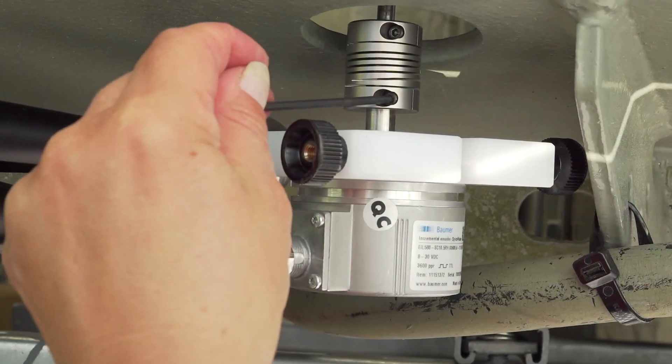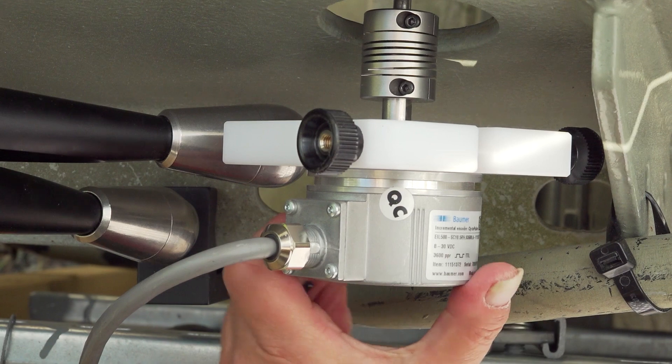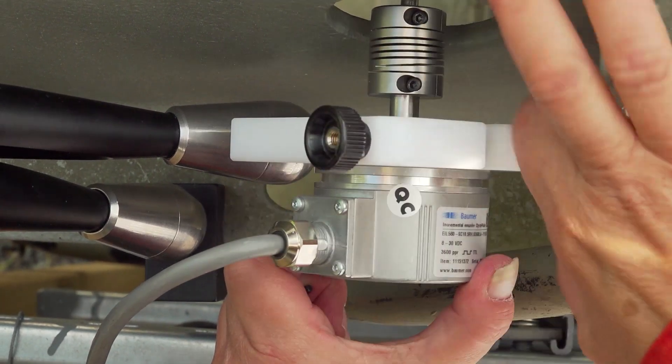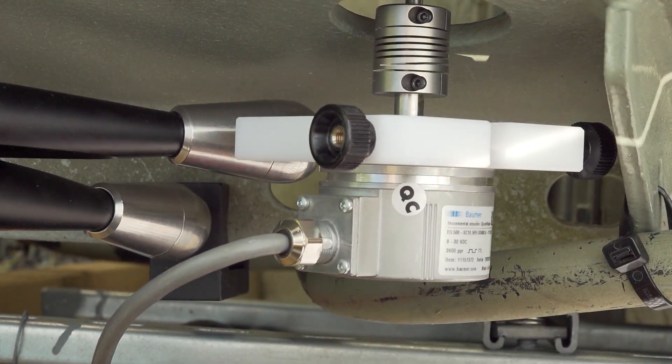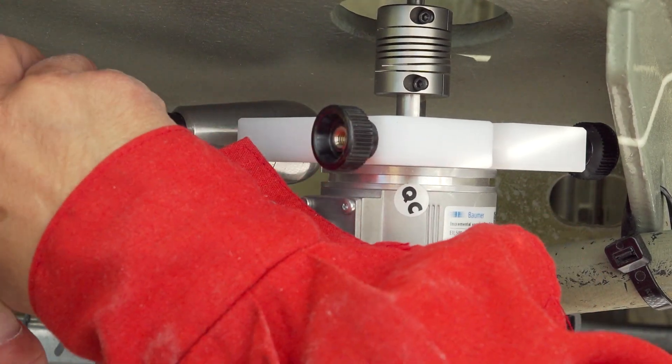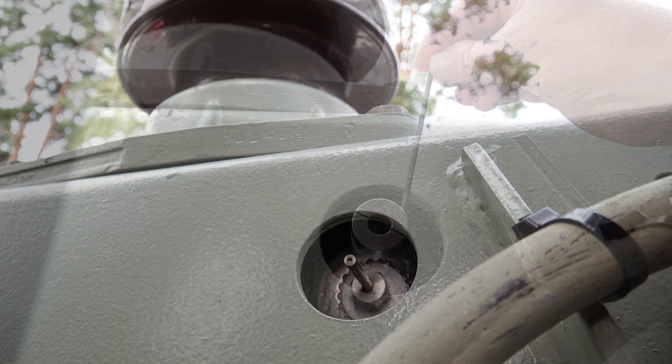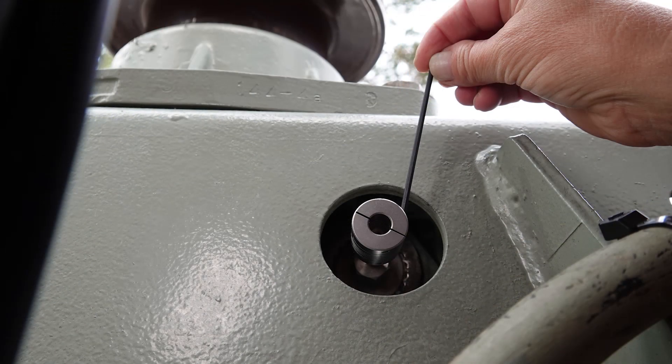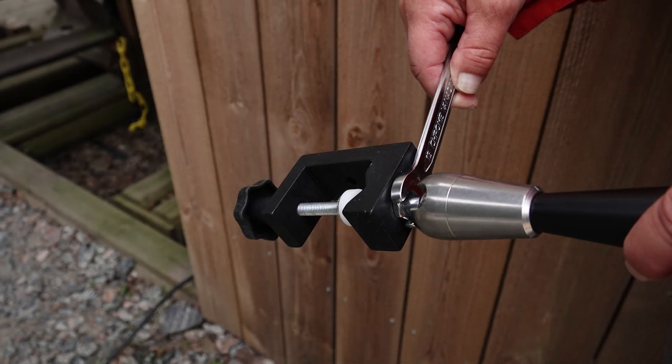Here I connect the motion transducer at the circuit breaker mechanism. Make sure it's not in the way for the moving parts of the circuit breaker. The adapter is mounted in an existing drilled hole in rotating point of the mechanism. Connect flex coupler to adapter. The mounting is very important for the final result.